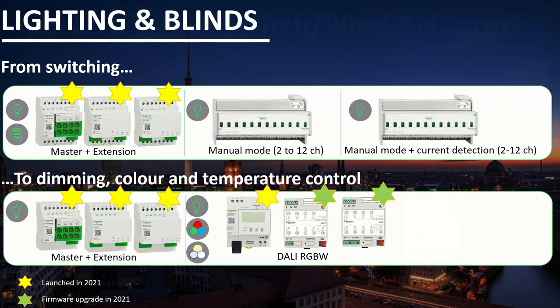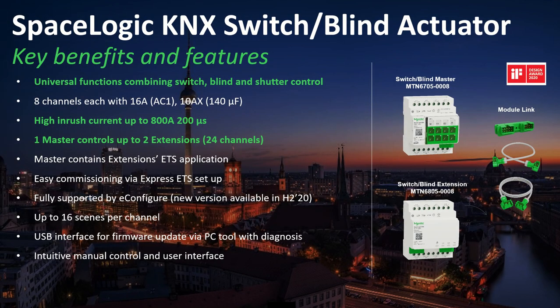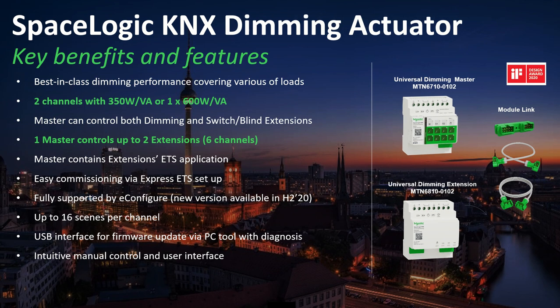Looking at the recently launched products in more detail — the SpaceLogic KNX switch and blind actuators offer universal functions combining switch, blind and shutter control all in one device, with high inrush current of up to 800 amps in 200 microseconds, and one master plus up to two extensions giving 24 channels. The SpaceLogic KNX dimmer actuators offer two channels with 350 watts per channel, or one channel with a full 600 watts, and follow the same master and extension concept with one master and up to two extensions, giving a total of 6 channels.